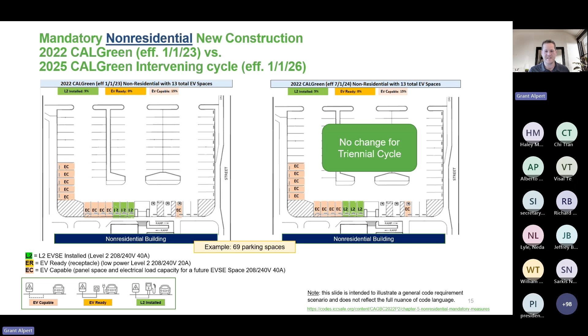With the power allocation method, here's some examples of the same parking lot, but with different power allocated to different chargers. So 69 spaces, here's that math, times 20% times 6.6 kilowatts, you have 91.1 kilowatts. Per the table that I showed you, you would use 85.8 kilowatts. And then from there, you can divide it up however you want. So you could have 40% of them being low power level twos with, I believe that says 20% or 10% EVSEs, or you can have 25 or 15% EV capable and 5% EVSEs, as long as the total power adds up to 91 or 85.8 kilowatts, then you're good.